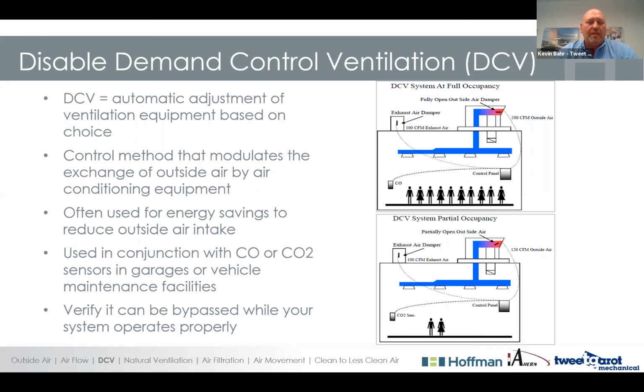So to override them, you are overriding a method that was installed to save energy. You will increase the amount of outside air by overriding them, typically. But please be cognizant that your system does go to a normal operating mode as a default. Some demand control ventilation systems have an override built right into them. Just confirm your system's overall operation if you do override them. Next slide, please.